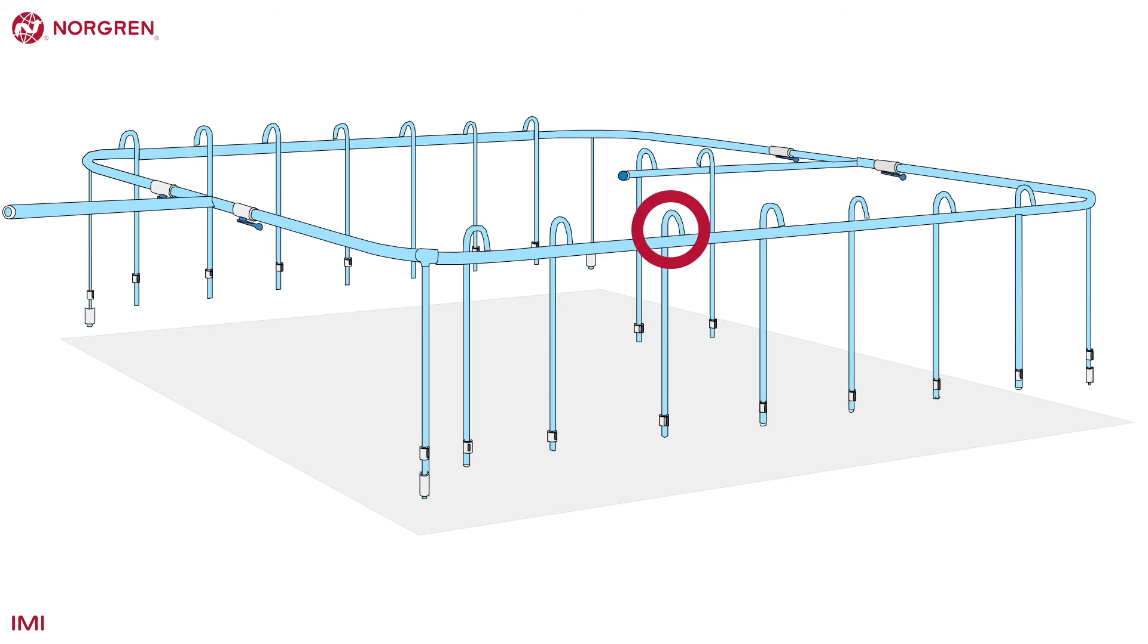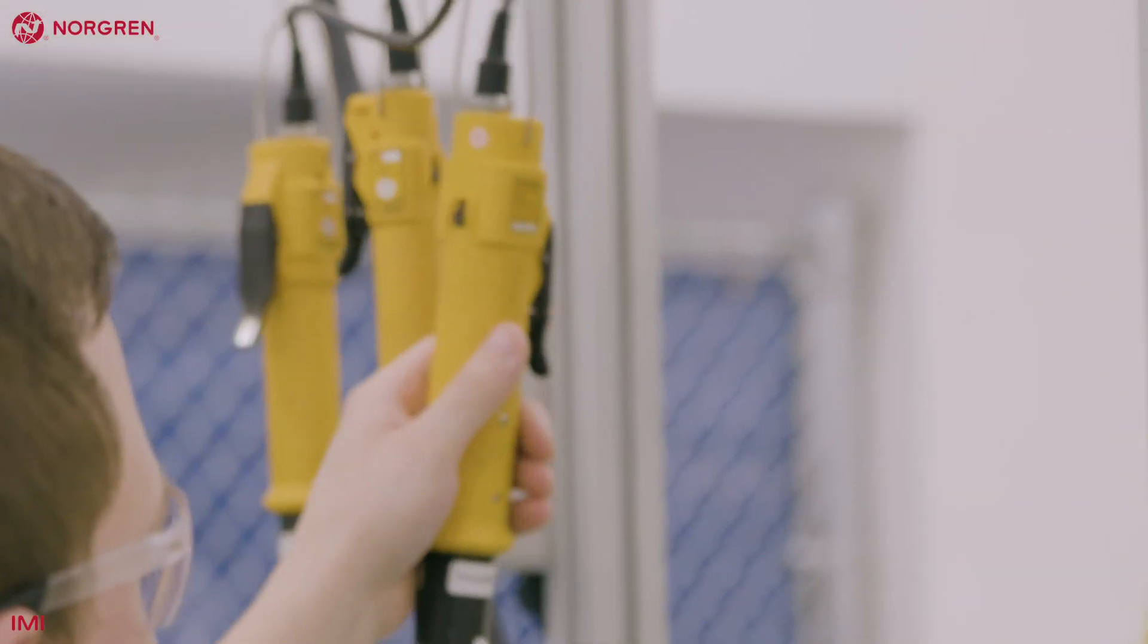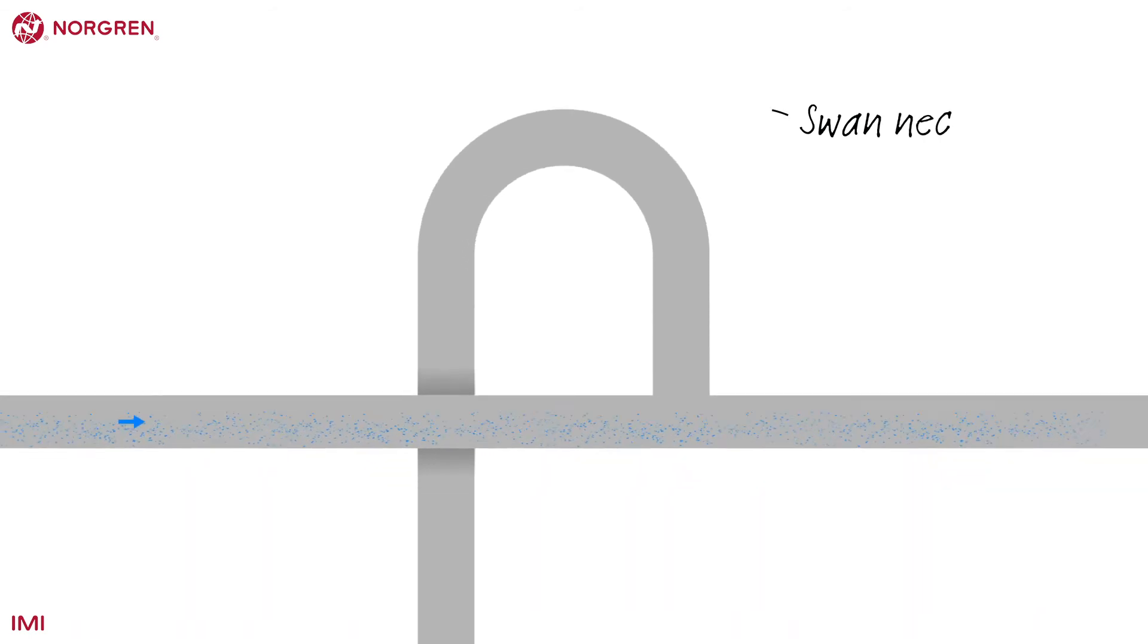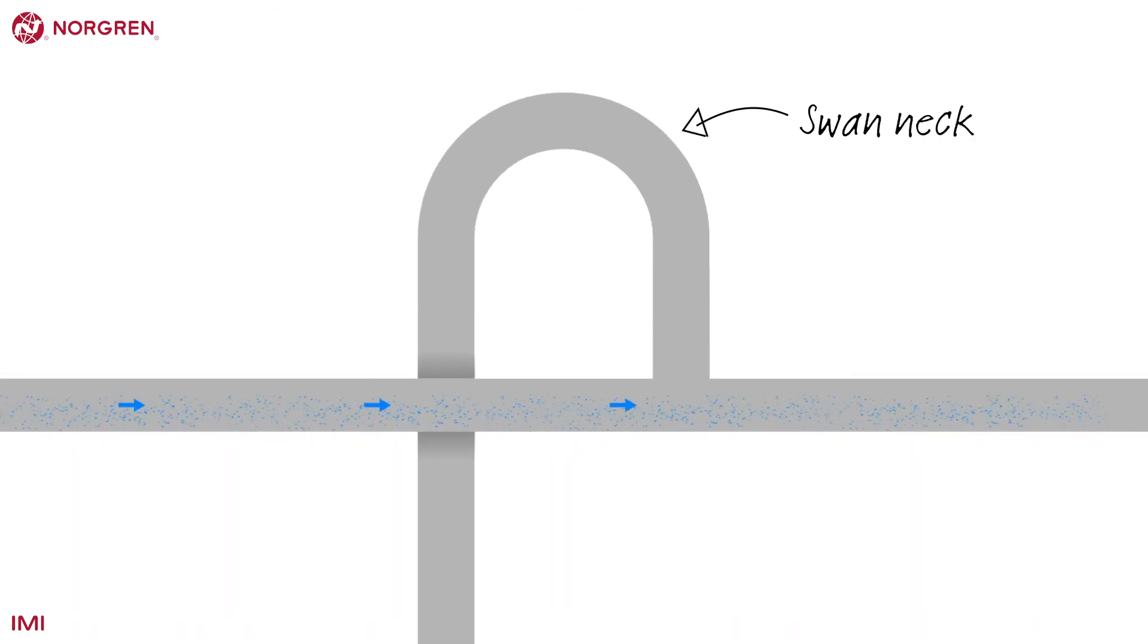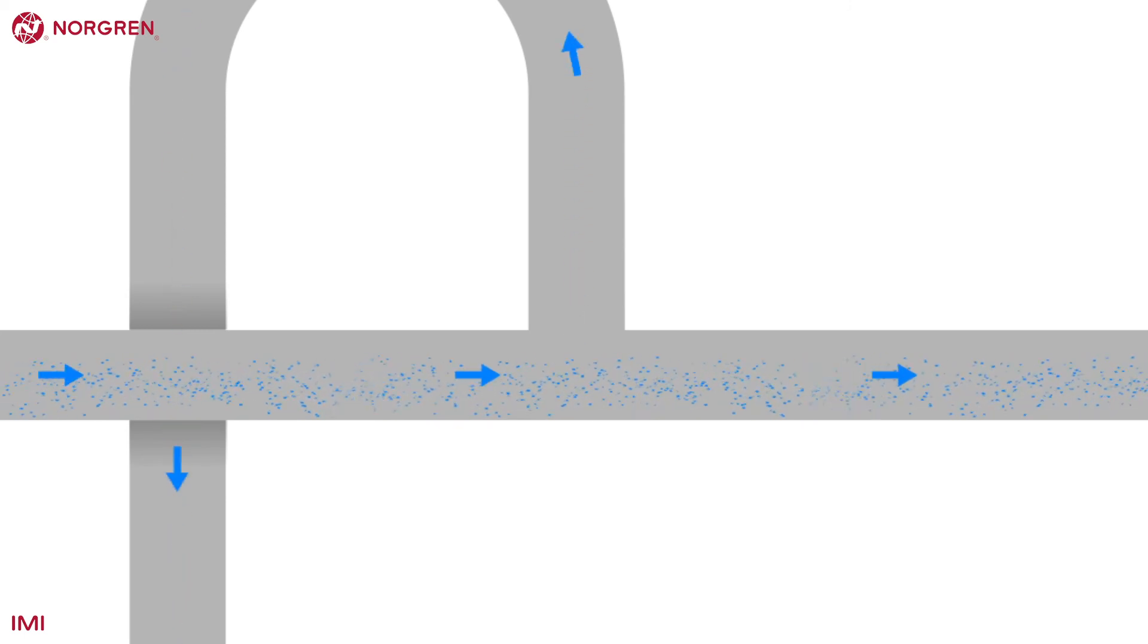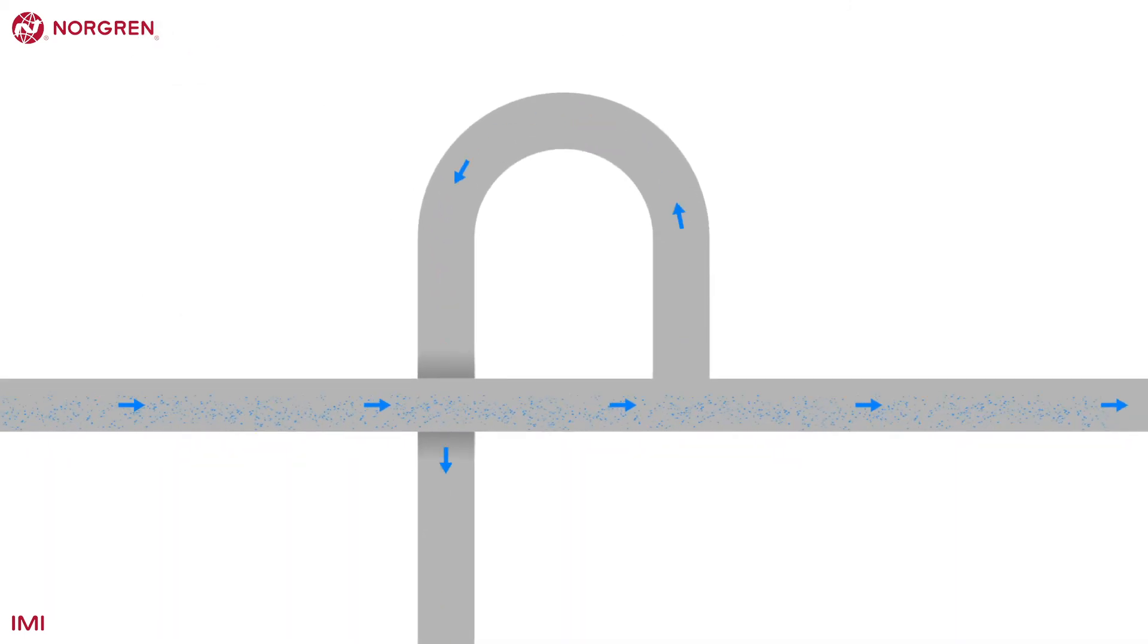The take-off points are where air is taken from the ring main to a point of use, typically a pneumatic tool, machine or bench. Notice the swan neck that comes from the top of the ring main. Taking air from the top will inhibit any fluid entering the downpipe and the swan neck provides the smoothest route for the air. Hard angles or elbows will slow airflow.